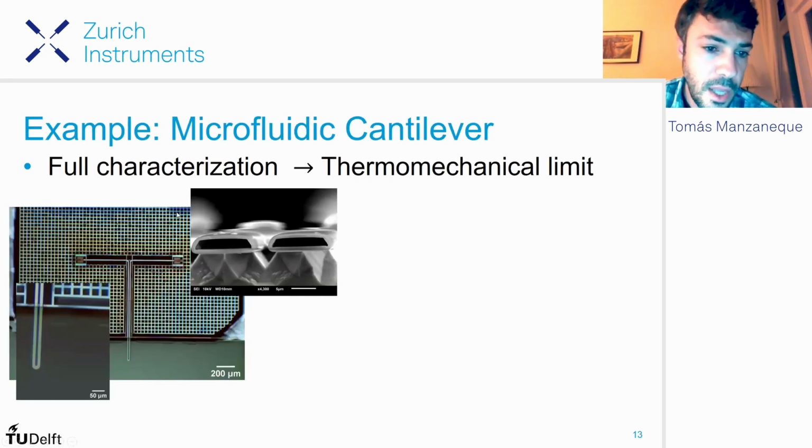To illustrate this process, I will show the data for these devices that we built in-house at TU Delft. They consist of a microfluidic channel. As you can see here, this is the microfluidic channel. There is an inlet and an outlet, and part of the channel is suspended, so it forms a resonator, a cantilever, in fact. You can see a zoom in here, and this is a cross-section of the suspended part, where you can see that it's hollow inside.